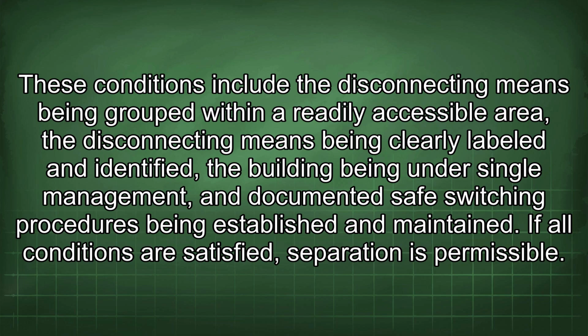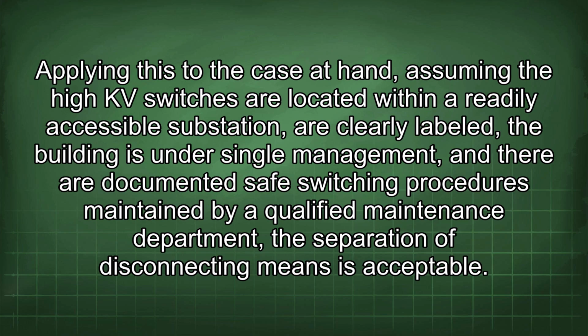These conditions include the disconnecting means being grouped within a readily accessible area, the disconnecting means being clearly labeled and identified, the building being under single management, and documented safe switching procedures being established and maintained. If all conditions are satisfied, separation is permissible. Applying this to the case at hand, assuming the high kV switches are located within a readily accessible substation, are clearly labeled, the building is under single management, and there are documented safe switching procedures maintained by a qualified maintenance department, the separation of disconnecting means is acceptable.